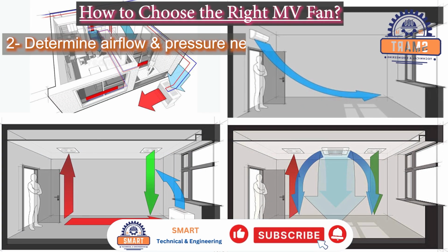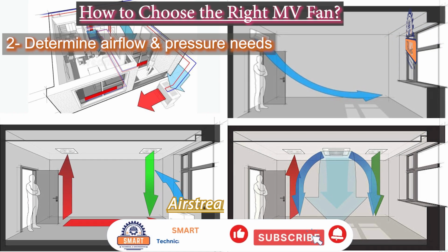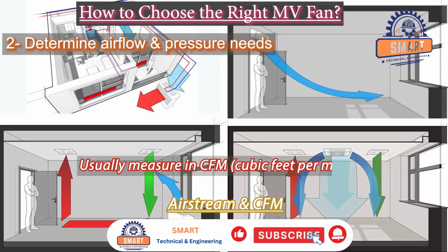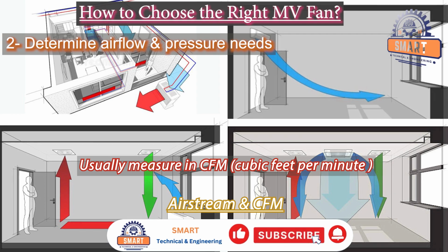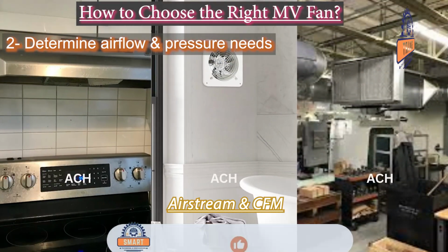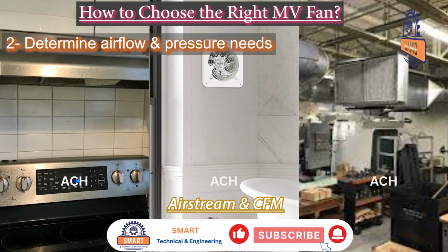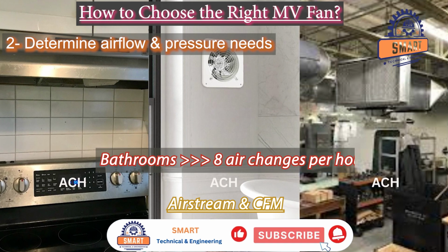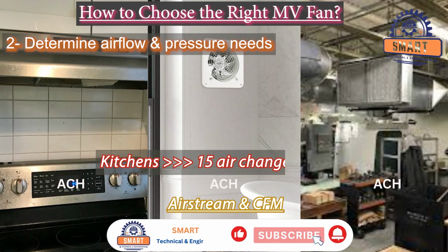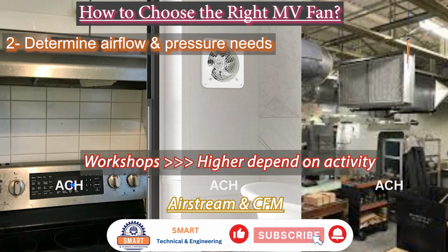Step 2. Determine airflow and pressure needs. Next, calculate the airflow requirement, usually measured in CFM, cubic feet per minute. You'll need enough capacity to exchange the air in the room several times per hour. As a rule of thumb, bathrooms need at least 8 air changes per hour, kitchens 15, and workshops even higher.